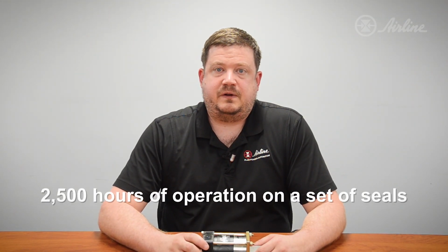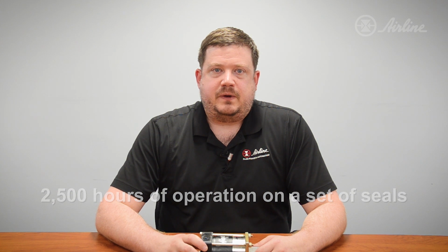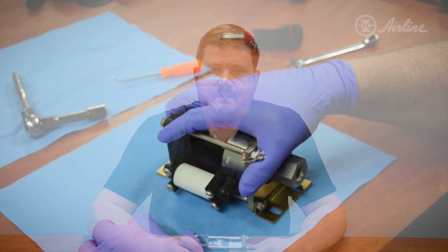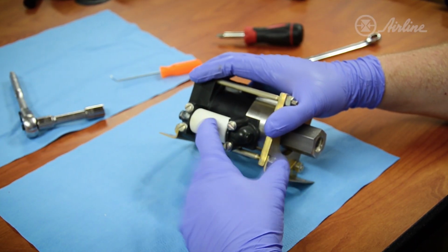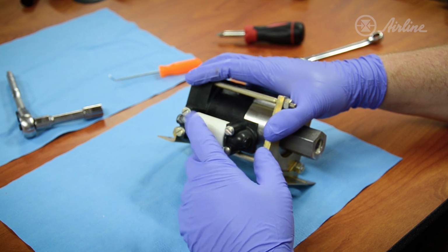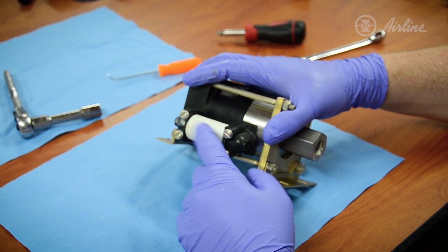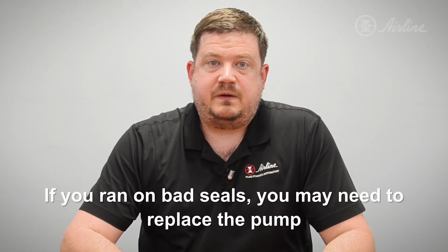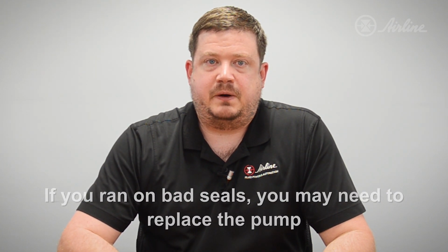Typically with this series, you'll get 2,500 hours of operation on a set of seals. After that point, you'll eventually start to notice some trouble maintaining pressure, and eventually you may even spring a leak in the pump. Also, any liquid seen coming through the muffler of the air drive section is a sure sign of seal failure. If you wait too long and run your pump on bad seals for a while, you'll start to damage the metal components inside the pump. And unfortunately, at that point, you'll have no other option but to replace the pump.